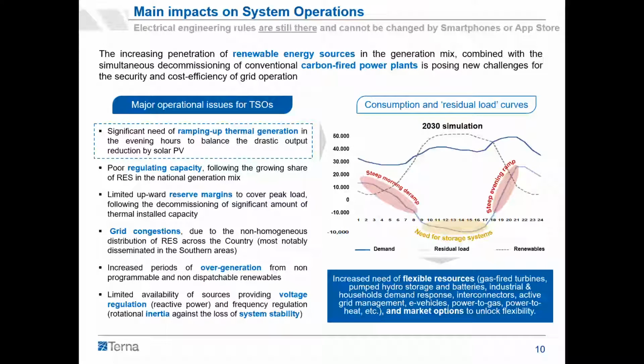Two years ago there was a blackout in Australia. In 1.5 seconds the system went down. When we had the blackout in 2003 in Italy, it took 20 minutes to reach blackout. There, with renewables, it took 1.5 seconds for half, a quarter of the country to go into blackout, because you no longer have inertia. With renewables there's an electronic inverter: frequency goes down, it shuts down. There are no rotating masses to absorb the shock and give you time to do something else.